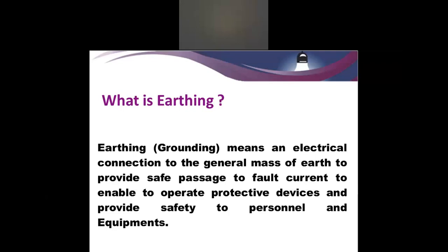But it is a different story - what is the difference between earthing and grounding? Let us assume earthing means an electrical connection to the general mass of Earth to provide safe passage to fault current, to enable protective devices to operate, and to provide safety to personnel and equipment. It covers everything - we have to ensure safety of personnel and equipment, pass fault current to the Earth, and that should be measured through our protective devices. This is why it is necessary.